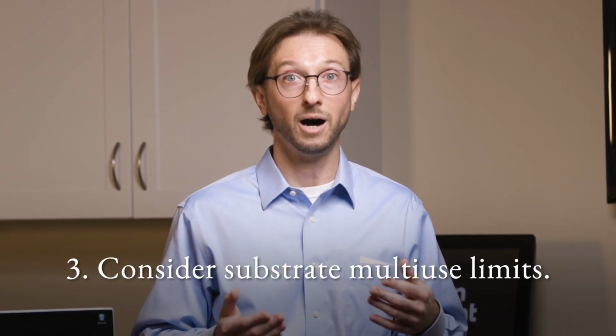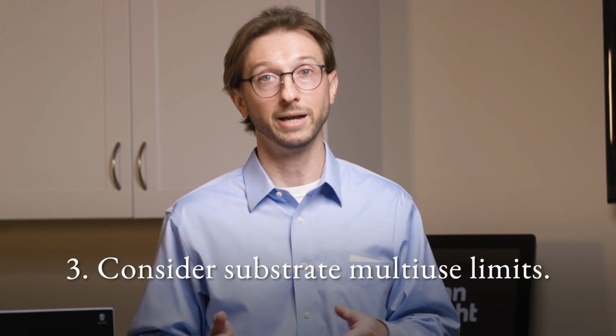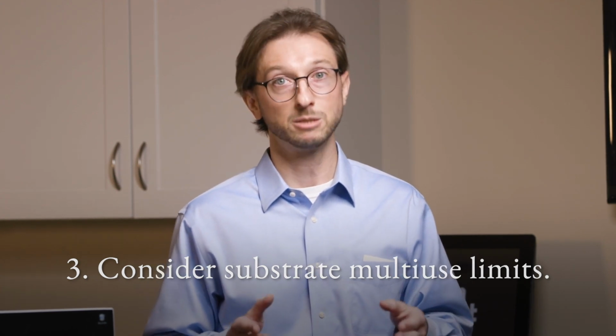A common question that folks have is about multi-use. Can you use these multiple times on different analytes or the same analyte? We don't recommend it for different analytes, but on the same analyte, you can actually use different parts of the real estate of this substrate because there is enough room there to potentially put on some additional aliquots of fluid that has the analyte in there. And you can also use the same substrate for a blank, as we saw in the demo, taking a blank water sample first on the same substrate and then bringing in the analyte to take a snapshot of that.